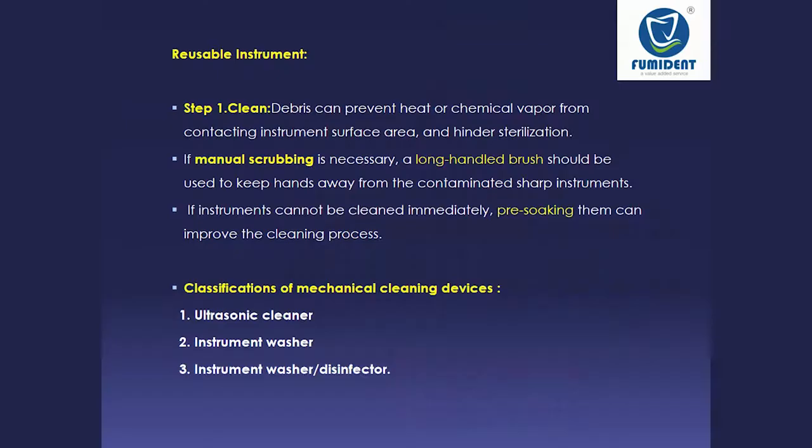Now after surgical or other non-surgical procedures, when you collect your instruments for cleaning, if your instruments are blood contaminated, or you can say soiled, you have to keep them in the disinfectant or at least in detergent water, so that the blood should not get dried out and should get neutralized so that its infectivity will get reduced. Then you have to clean them properly. Now there are 2 methods for cleaning. One is the manual method and another is ultrasonic cleaning. For the manual method, as most clinics use the manual method, you have to use a long handle brush so that your staff will not get injured.